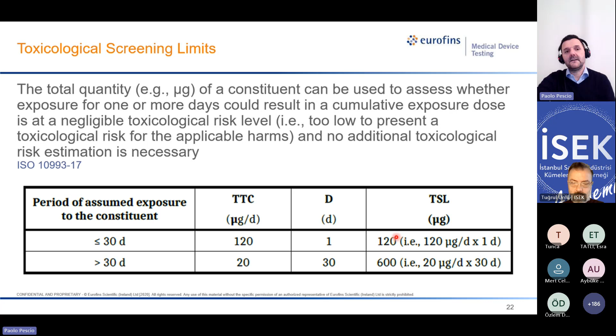What is the total quantity? The total quantity is the quantity coming from usually an exhaustive extraction. From time to time, we can also use exaggerated conditions compared to the clinical use. We can even use simulated use extraction, but we need to be sure that the extraction conditions are conservative relative to the intended use of the medical device. When we perform an exhaustive extraction, we are sure that we are conservative, and the quantity extracted after an exhaustive extraction can be considered the total quantity. It's called TQ, the total quantity.